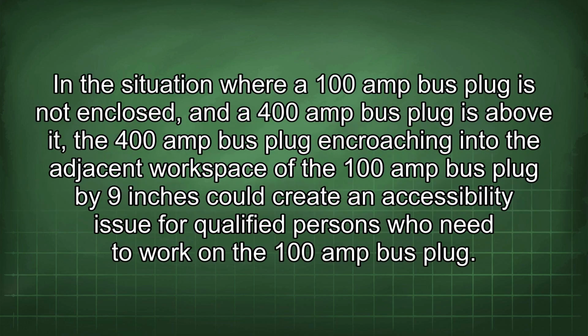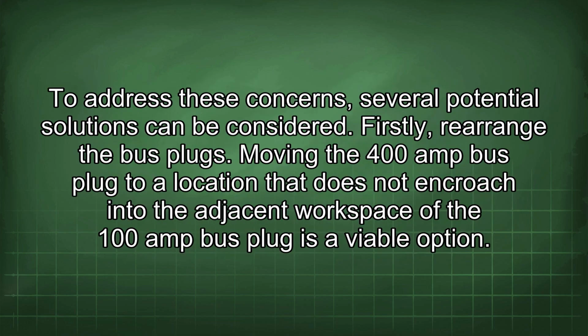In the situation where a 100 amp bus plug is not enclosed and a 400 amp bus plug is above it, the 400 amp bus plug encroaching into the adjacent workspace of the 100 amp bus plug by 9 inches could create an accessibility issue for qualified persons who need to work on the 100 amp bus plug. To address these concerns, several potential solutions can be considered.